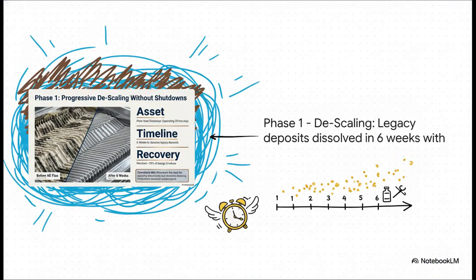Phase 1 was descaling, and this is incredible. Look at the before and after of their plate heat exchanger. That thick, caked-on, old-school scale was completely dissolved in just 6 weeks. And the best part? This happened while the system was running. 0 shutdowns, 0 chemical cleaning, 0 interruption to production.